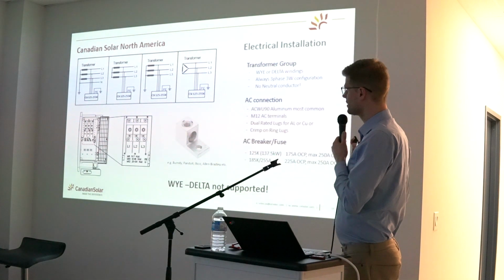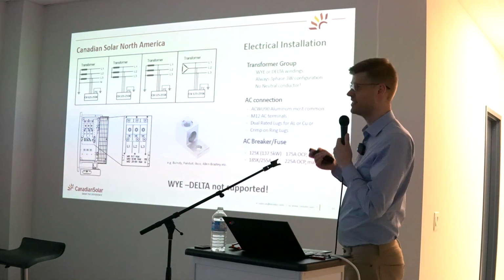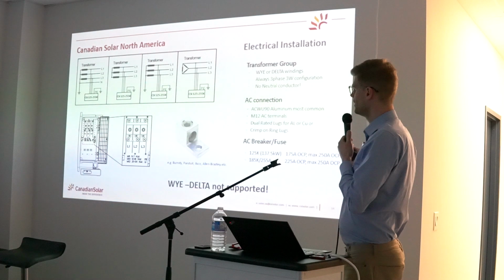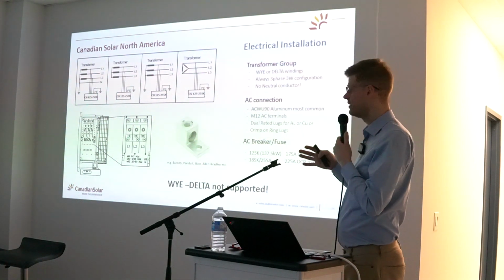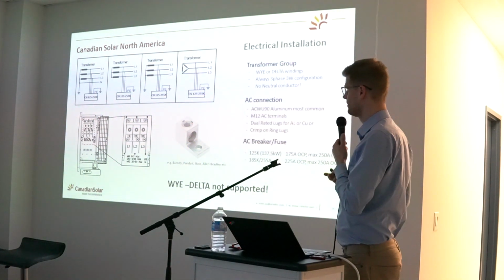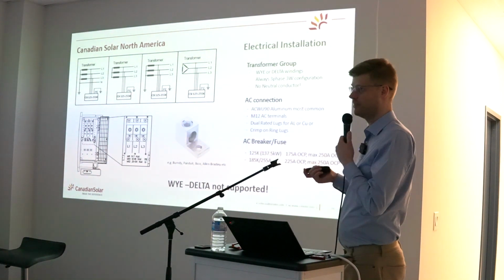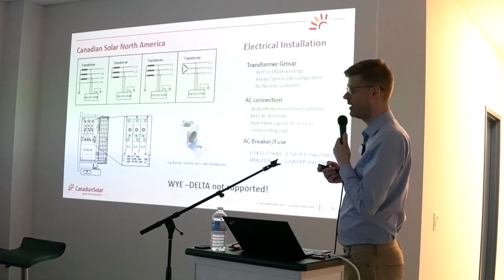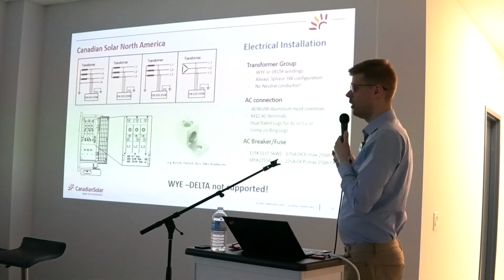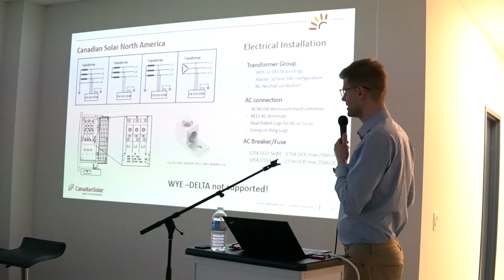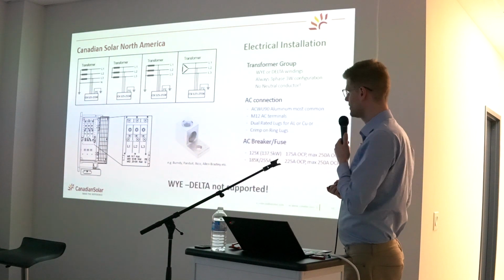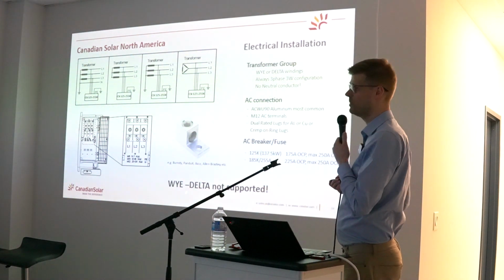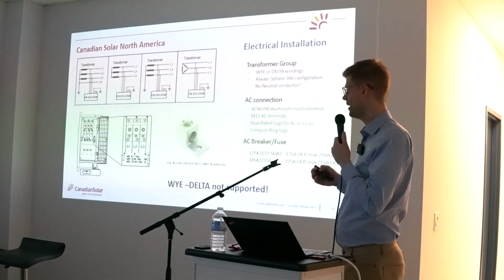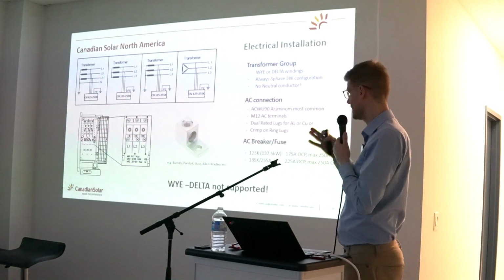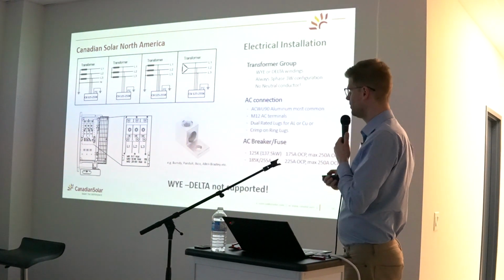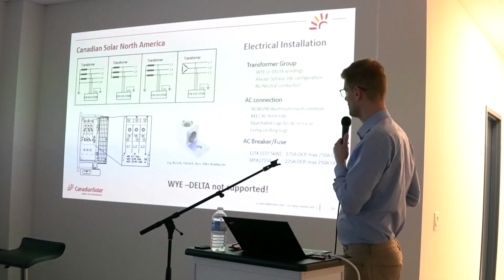What grid connection can it be installed with, or what secondary side of the transformer? The unit by default is a 3-wire, 3-phase system plus ground. So you can have pretty much any configuration on the secondary side, a Y or a delta. The only limitation CSI has, if you look at the entire transformer, is that the primary side cannot be a Y configuration. So as long as you have a YY or a delta Y or delta delta, things work out, but a Y delta is one of the only exclusions you have.